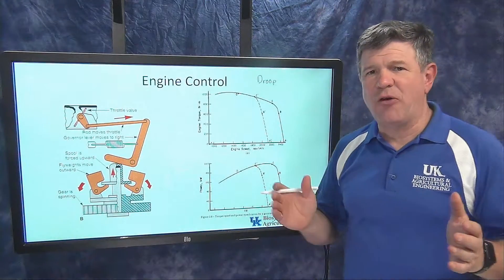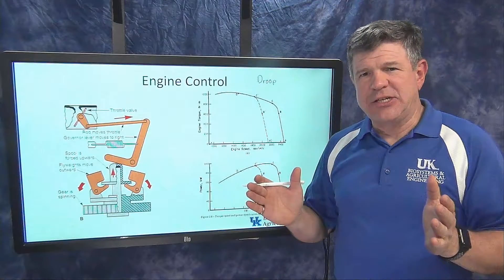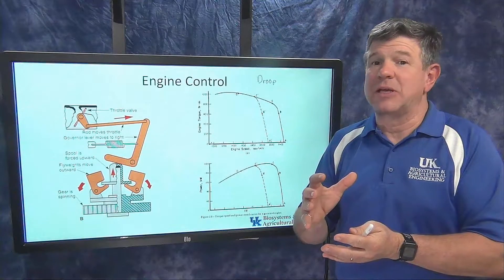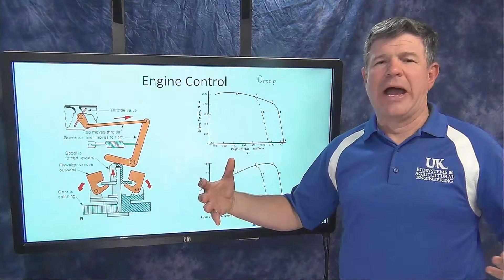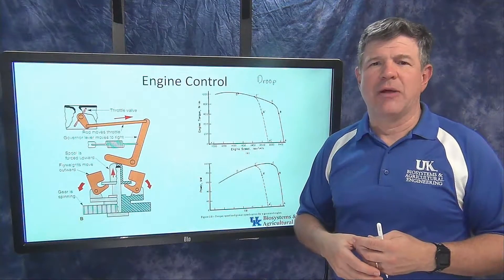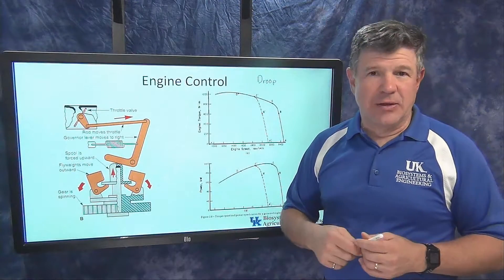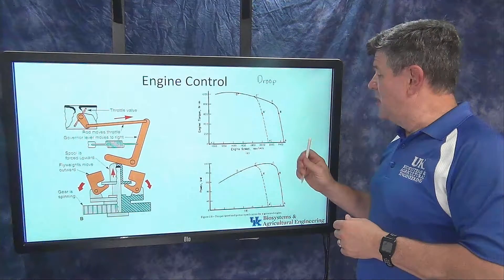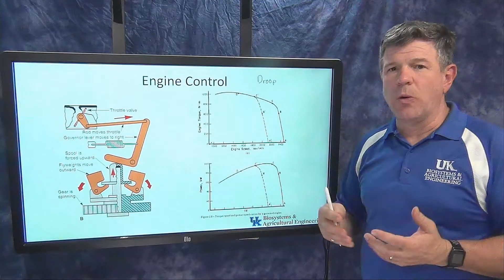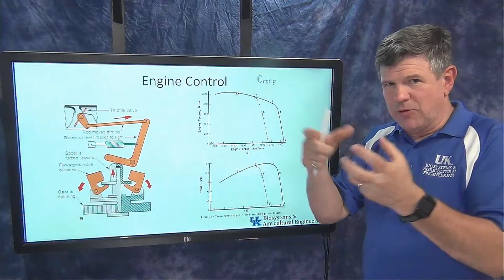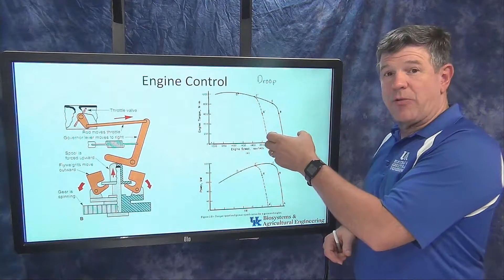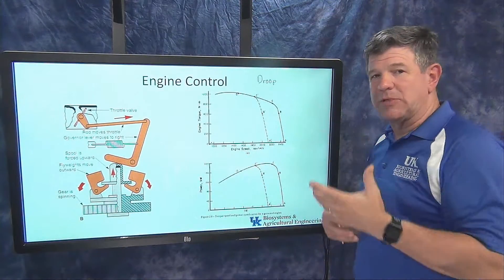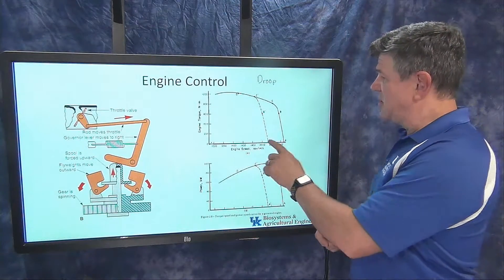The governor droop is how much speed change there is from when the governor is completely closed down — as fast as it can go with basically no power demand on the engine — to where it is wide open, where the governor can't do anymore and the engine's torque control takes over. It's how much the speed changes as the engine goes from maximum speed with no load, where the throttle plate or fuel flow is closed, to where the throttle opens all the way to the point where that's all the governor can do.